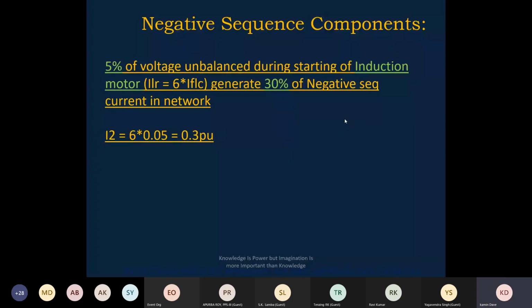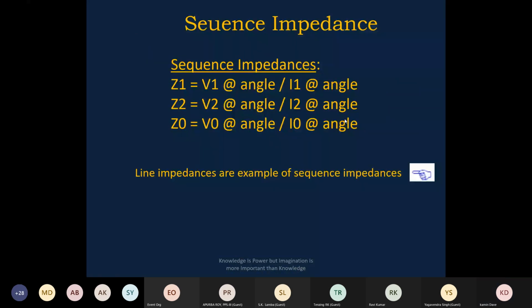5% of unbalanced voltage creates 30% of negative sequence current in a network during motor start conditions. Similarly, when we talk about sequence components, there are positive sequence voltage, negative sequence voltage, zero sequence voltage, positive sequence current, negative sequence current, and zero sequence current. Similarly, we can also see the sequence impedances.